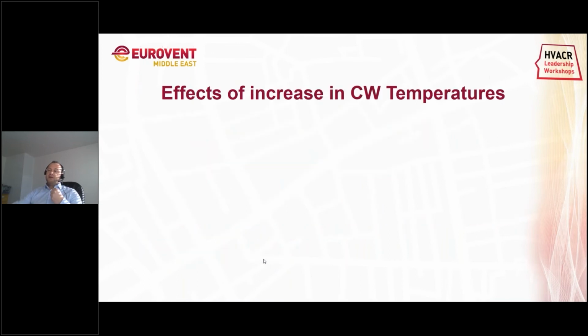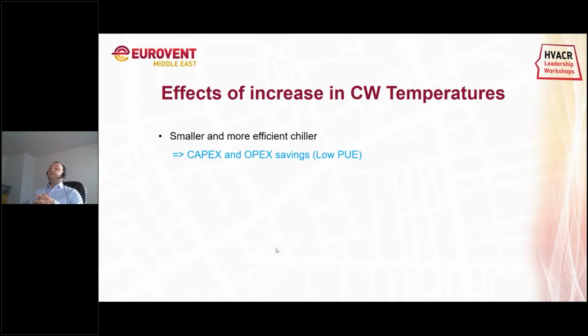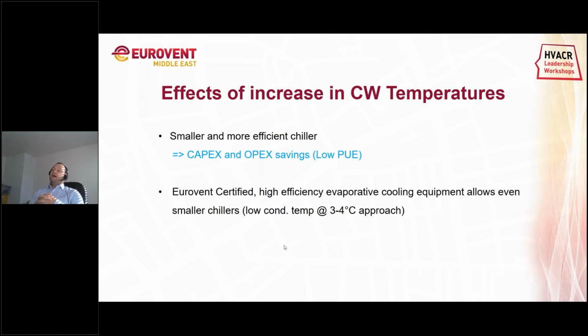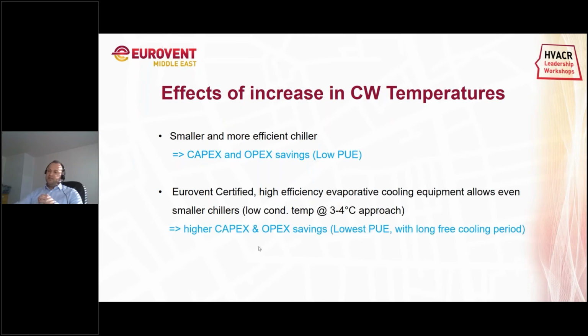What do these effects of an increase in chilled water temperatures mean? First of all, the capacity of the chiller will increase, or we can select smaller chillers. A chiller is responsible for, let's say, 80% of the energy consumption of the water-cooled system, so you can see there is a big saving. You will also have a more efficient chiller, as you can reduce the condensing temperature of your chiller. So we have a capex and an opex saving, and we can have a low PUE. When you use, on top of that, Eurovent certified high efficiency evaporative cooling, you can even provide lower condenser temperatures to your chillers by using a very small approach. The result is that you can have even higher capex and opex savings, which can lead to a much lower PUE and even long free cooling periods.